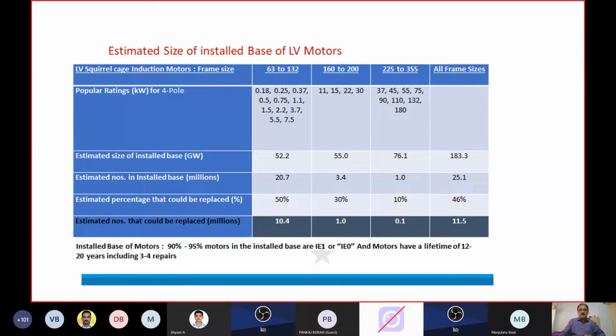If you look at the total population of motors, we have about 2.5 crore motors installed in our country. 25.1 million is 2.5 crores. This is the total population of motors considering all frame sizes. And if you look here, 63 to 132, generally called small motors, that is between 0.18 kilowatt to 7.5 kilowatt, they constitute approximately 83% of the total population available in the market.